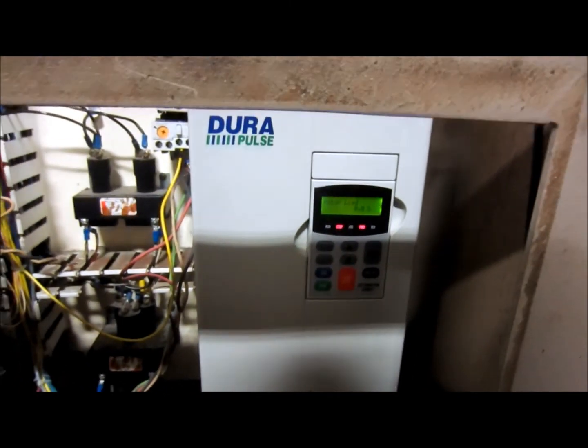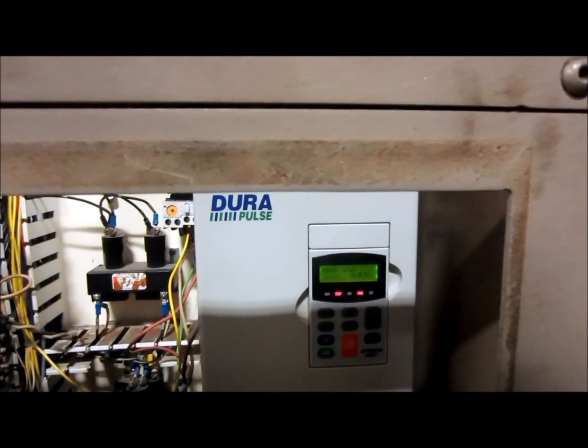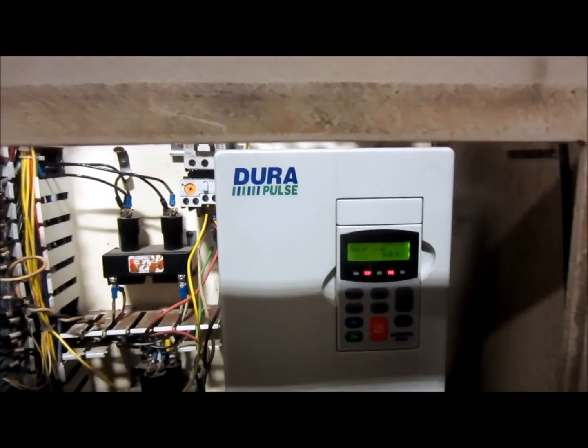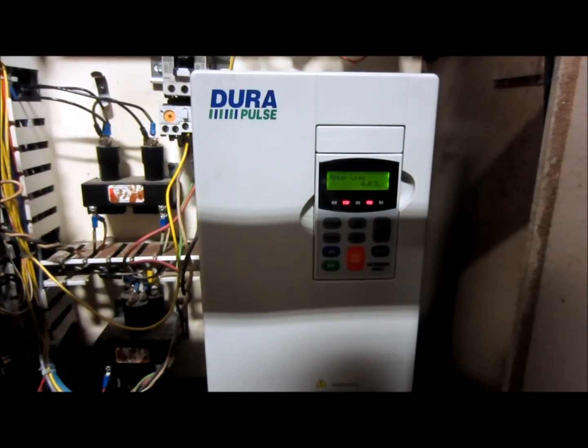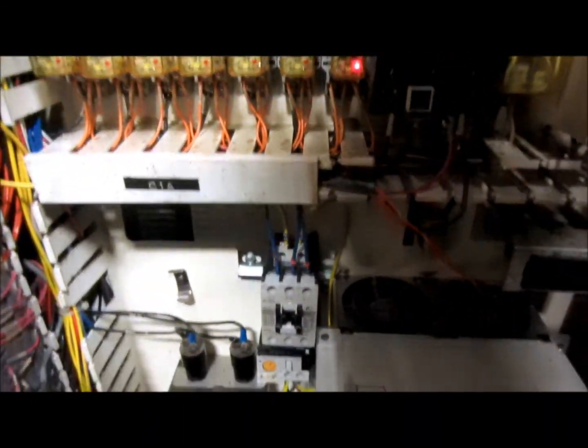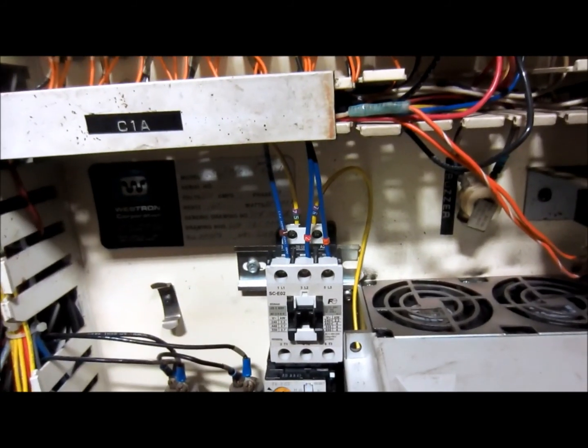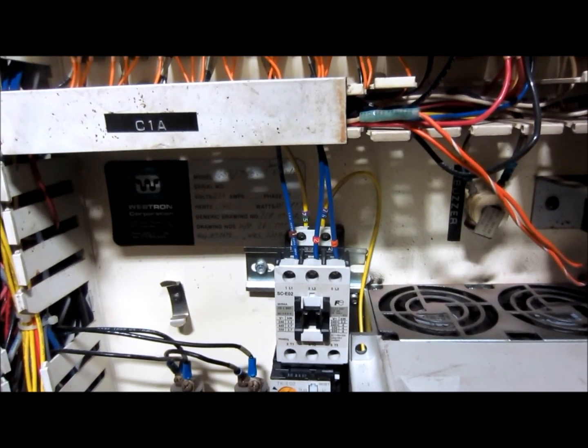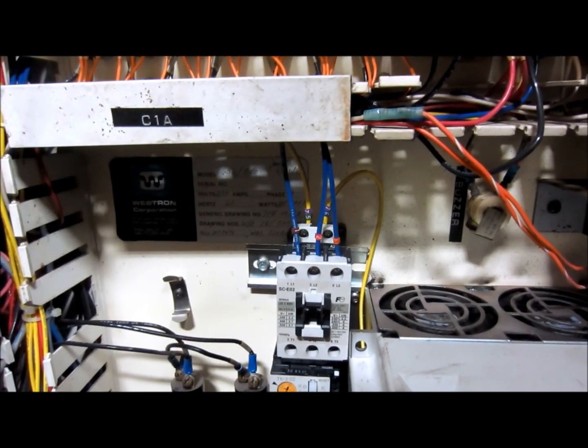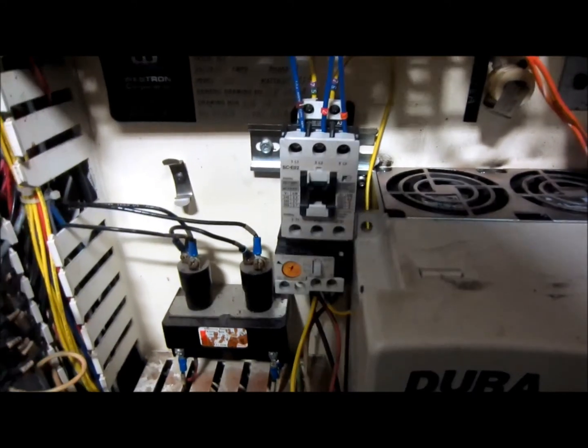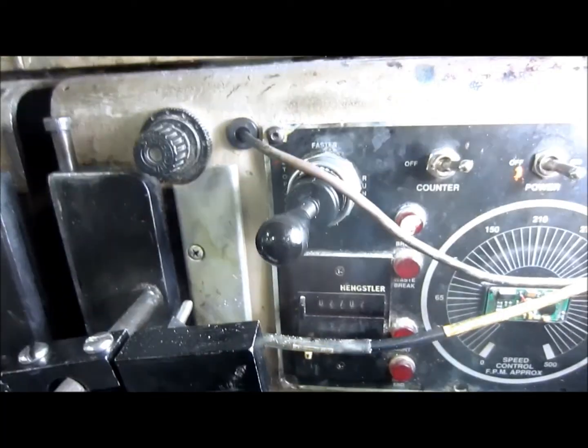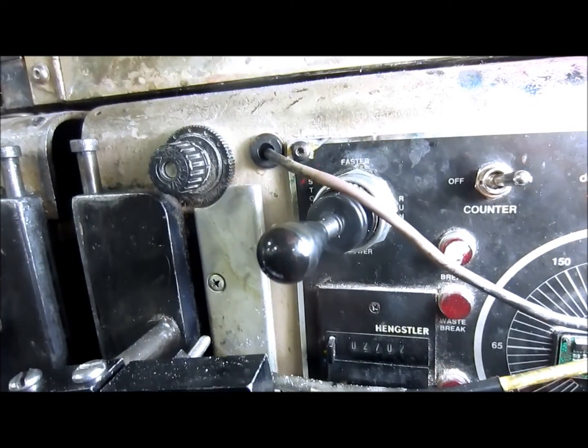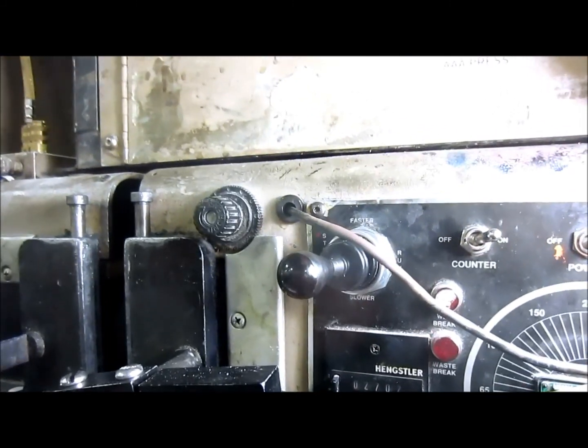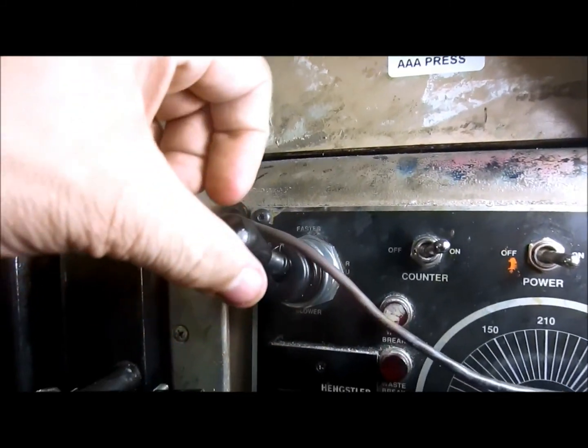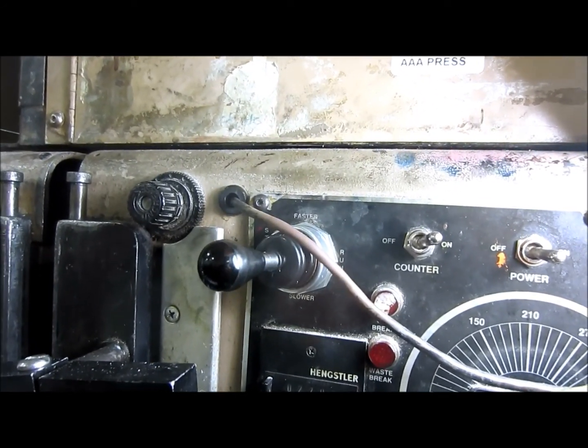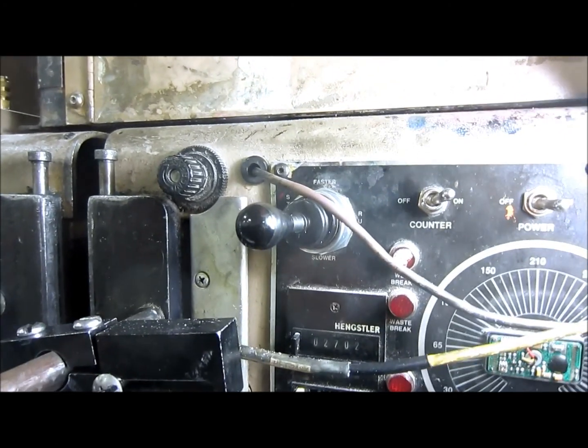Durapulse GS327P5 drive, and it's used to actually operate this machine. It drives the motor that I just showed you. And right next to it, I have a SC-E02 contactor and a TK-E02 overload, and that's used for the dryer motor, which I just showed you. The other advantages of that drive is that it's programmable to make use of the faster and slower positions of the original joystick. The speed of this machine can be controlled from 3 points.